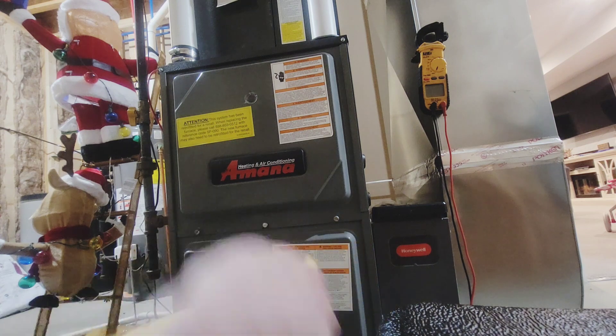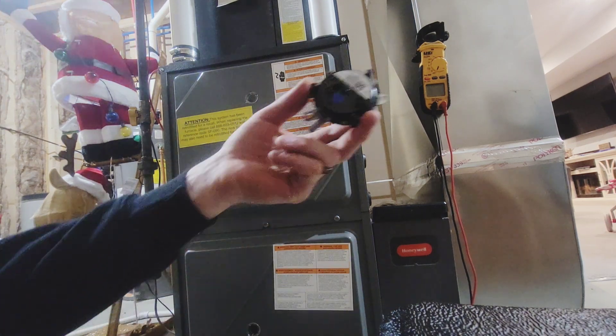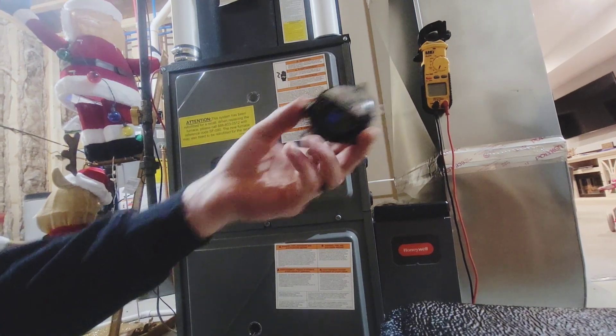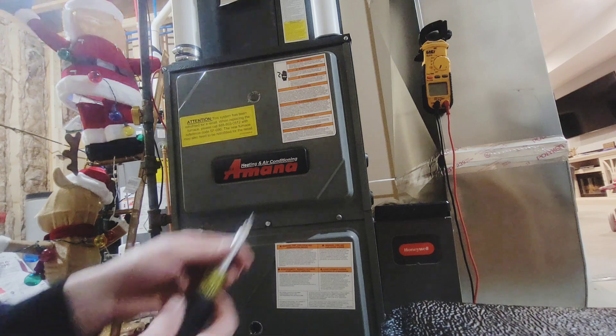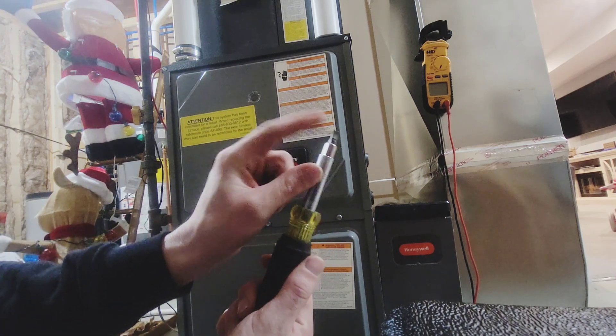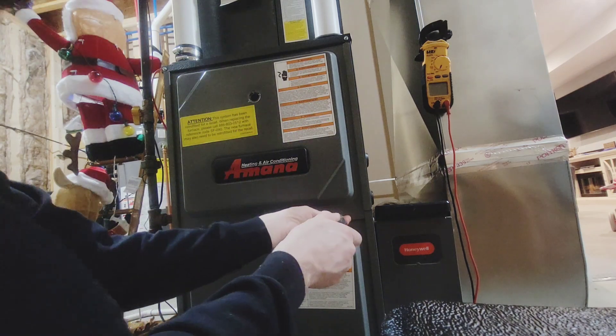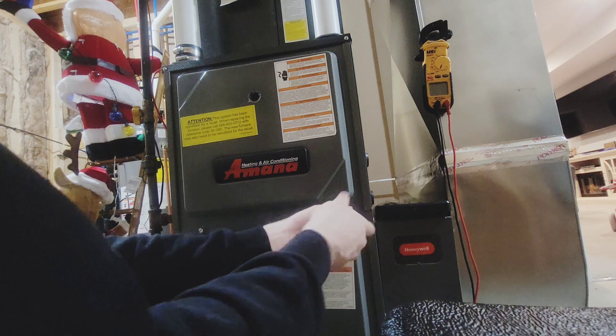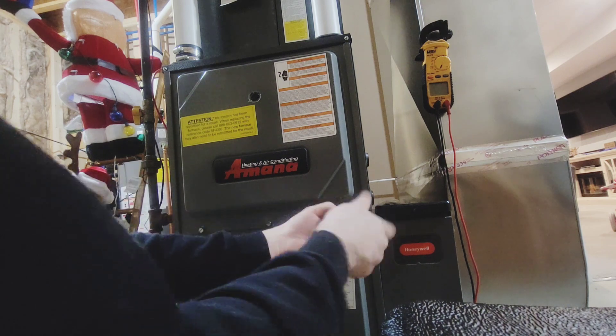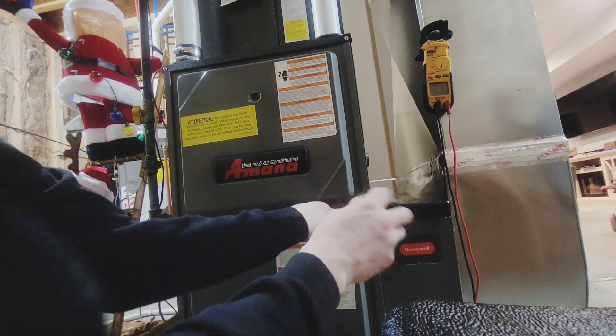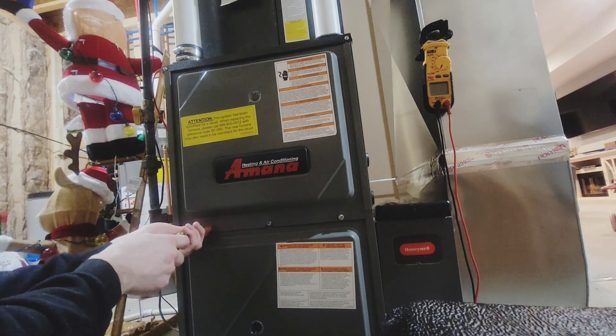First one we diagnosed a clogged drain line, the furnace side itself going to the trap from the collector box. Furnace got waterlogged, drained out the inducer motor, cleaned the trap, cleaned all the drain lines and ports.